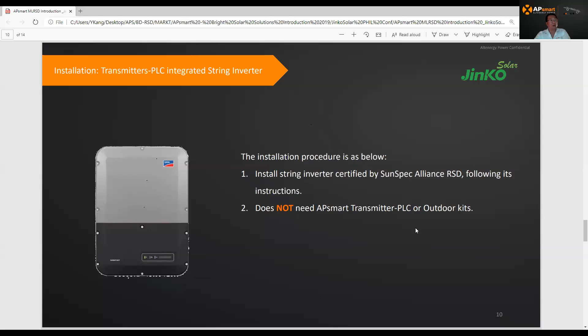So you can see the key point on the CT limitation, which means it's a 10 string, right? But the real limitation actually is 150 amp per CT. So for instance, if you have a system design where each string has about 10 amp or less, you can actually go over the 10 string limit. You could have 10, 11, or 12 strings, as long as your overall current is less than 150 amp, it should be okay.